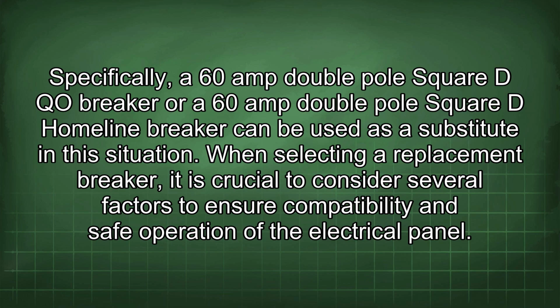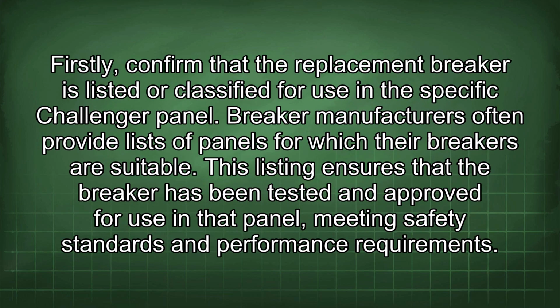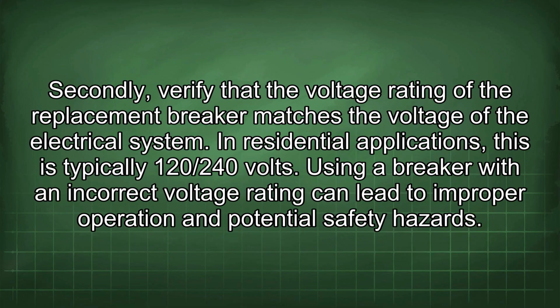When selecting a replacement breaker, it is crucial to consider several factors to ensure compatibility and safe operation of the electrical panel. Firstly, confirm that the replacement breaker is listed or classified for use in the specific Challenger panel. Breaker manufacturers often provide lists of panels for which their breakers are suitable. This listing ensures that the breaker has been tested and approved for use in that panel, meeting safety standards and performance requirements. Secondly, verify that the voltage rating of the replacement breaker matches the voltage of the electrical system.